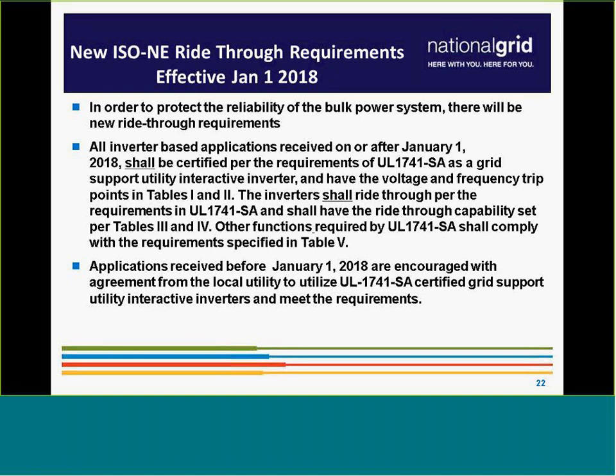Because of that, and through the IEEE 1547 process, there's a real need for voltage and frequency ride-through. When there's a system disturbance, two things happen: voltages drop and frequency drops. So you want to make sure that when they're dropping to a certain point, the big generation stays online.